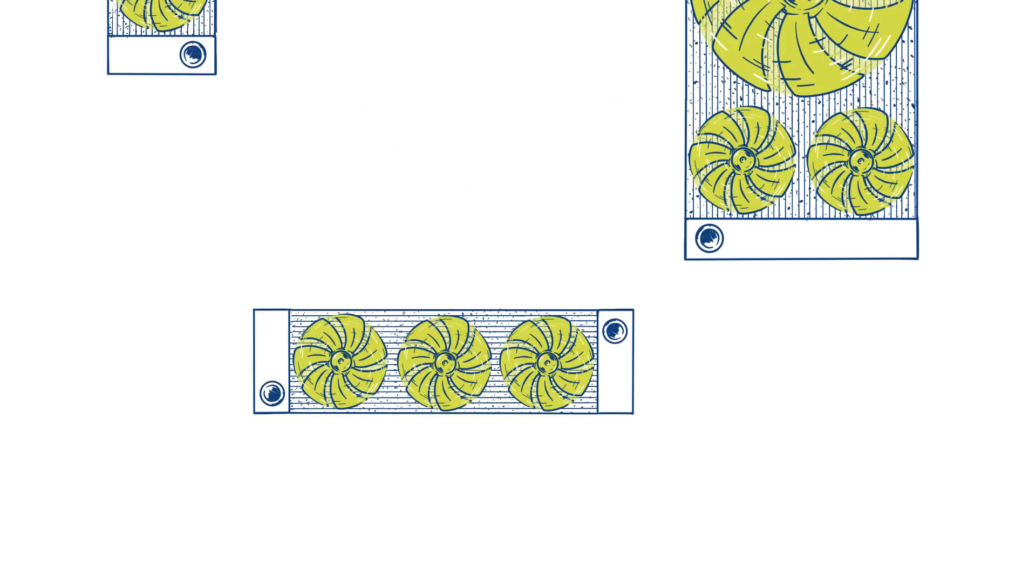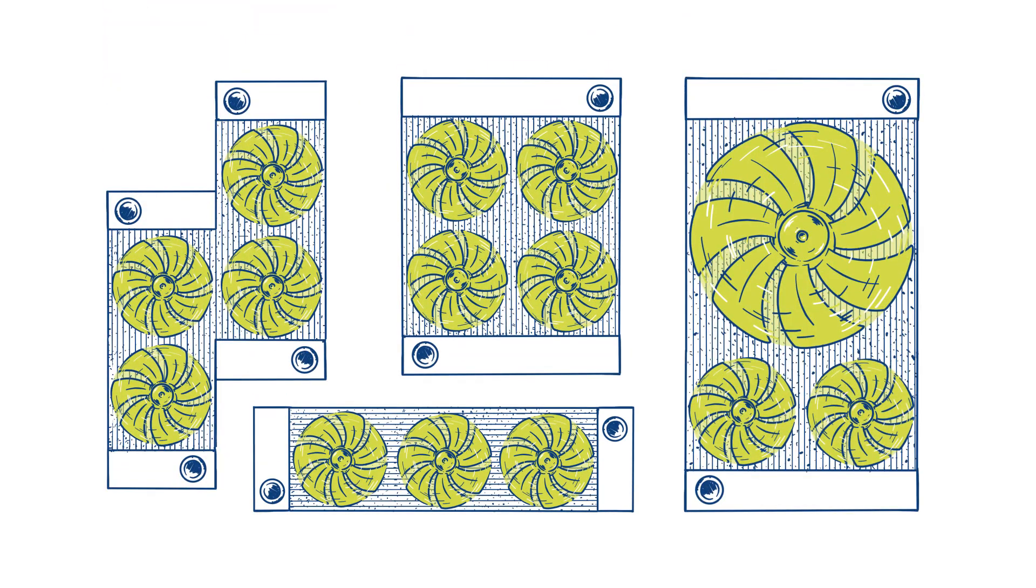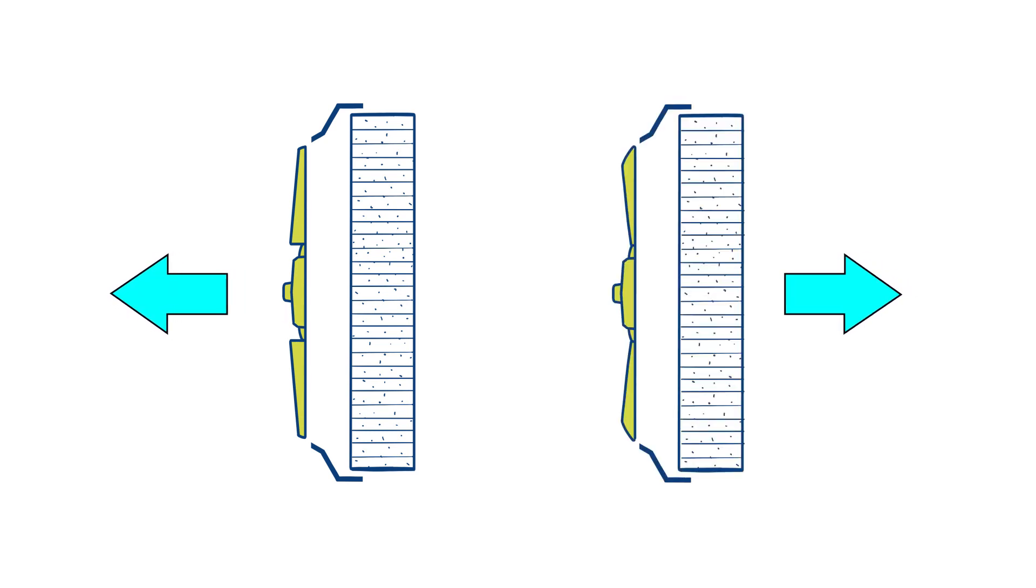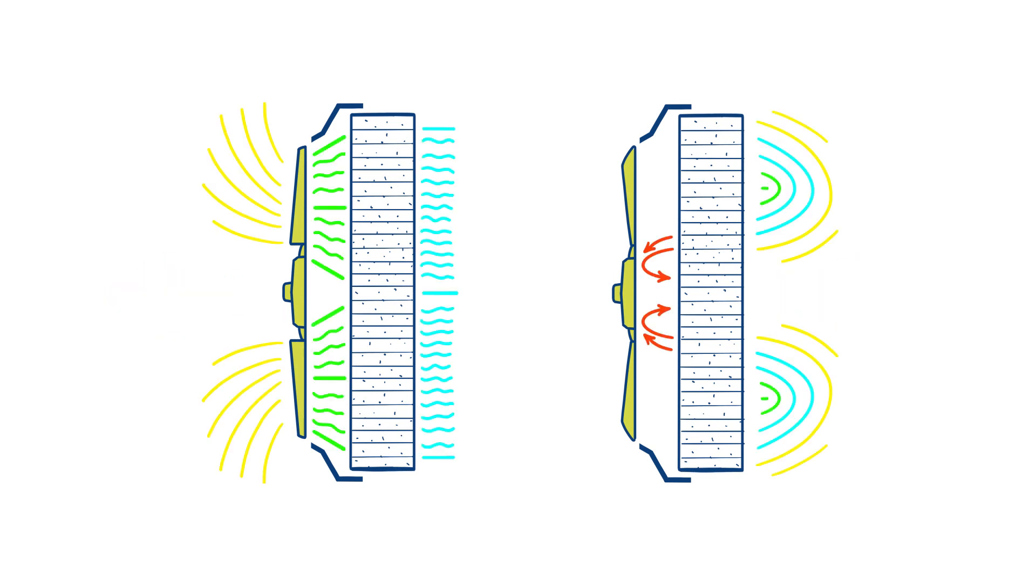Of course, the fan selection depends on the available shape of the cooler. A suction fan is preferable to a blowing fan because it requires a lower plenum thickness and ensures better cooling air distribution on the core surface.